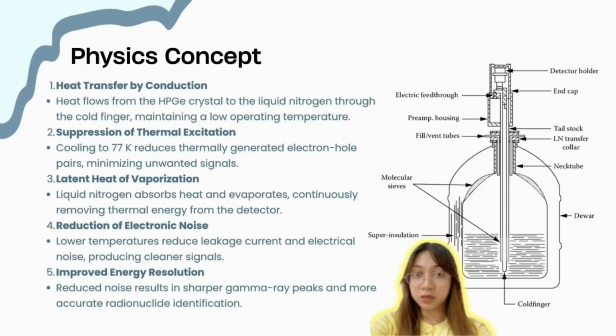Another important concept is the latent heat of vaporization. Liquid nitrogen absorbs heat from the detector and evaporates. This phase change continuously removes thermal energy while keeping the temperature nearly constant. As a result of the low temperature, electronic noise and leakage current are significantly reduced. This produces cleaner electrical signals and improves the detector's performance. Finally, the reduction in noise leads to sharper gamma ray peaks, allowing more accurate identification and analysis of radionuclides. Therefore, liquid nitrogen cooling is essential for achieving the high sensitivity and excellent energy resolution of HPGE detectors.